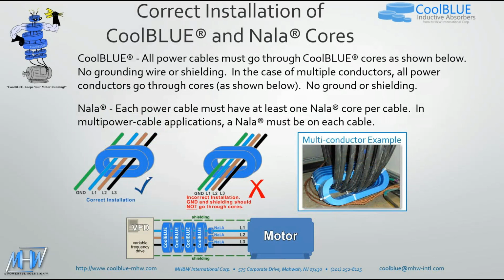When do you use the NALAs? What's the reason, or what's the break point for putting those on? All the time. There is no break point. The NALA adds in with the dV/dt filtering and some of the noise suppression. So it's recommended that they're installed on all applications because the whole solution is really a combination of the two cores put together. It's like trying to eat a peanut butter and jelly sandwich without the jelly. It just doesn't work.